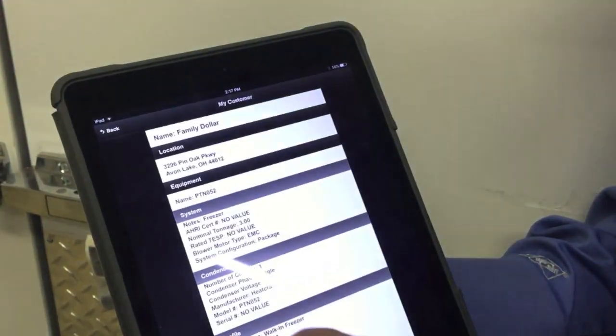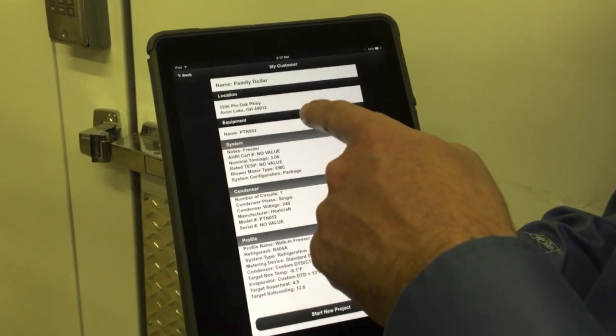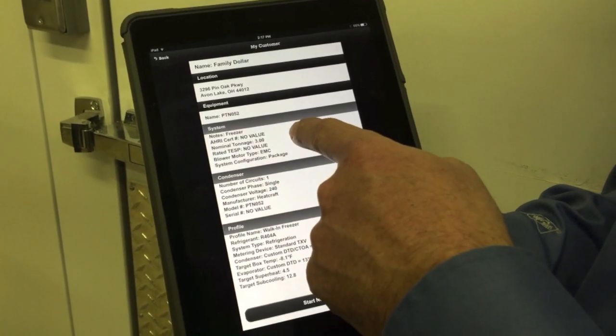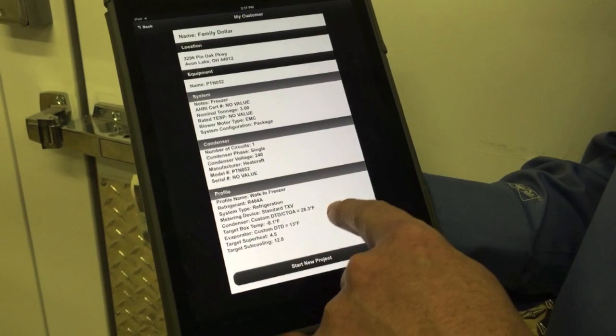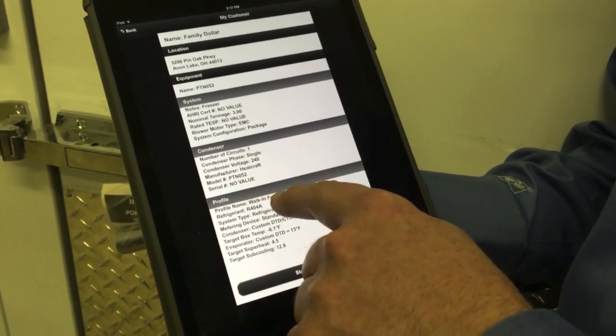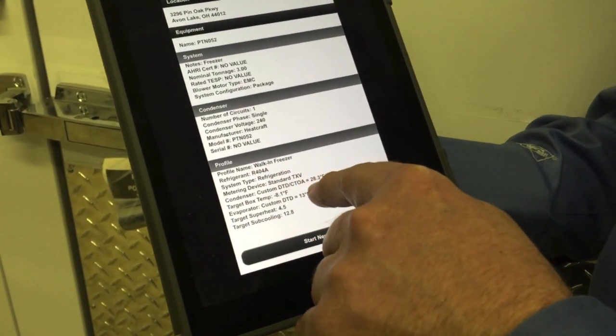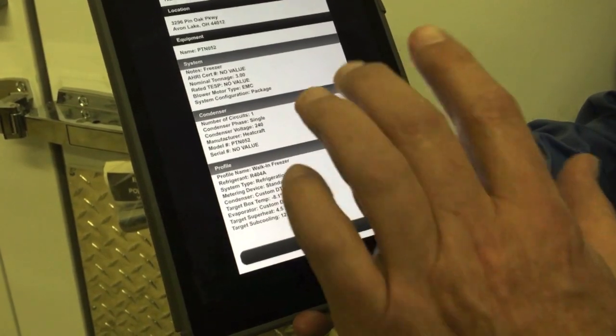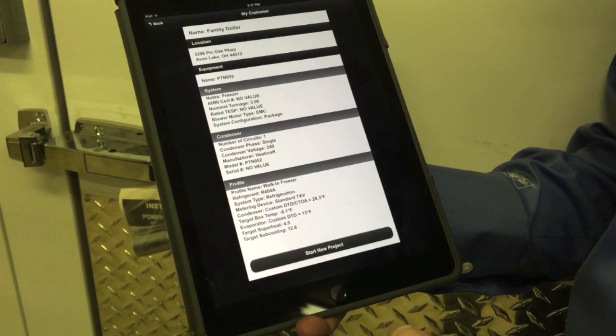We're going to go ahead and select that unit. When we pull that up, it allows us to verify the location, the equipment, model number, serial number, any notes about what type of system it is, the condenser. More importantly, it pulls in the profile of the system. We can see this is a walk-in freezer, 404A with a standard TXV, and it pulls in the design temperature differences from the benchmarks — the exact design temperature differences we set the equipment up with initially.